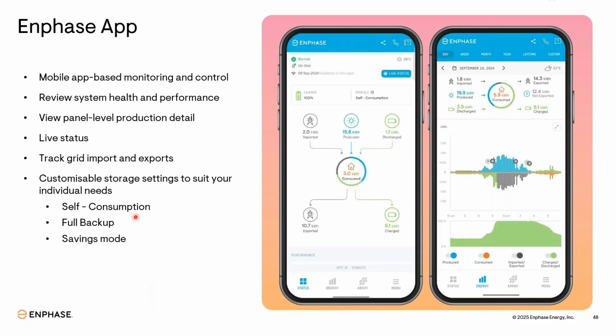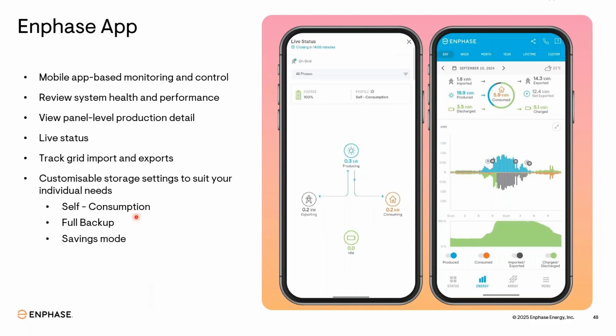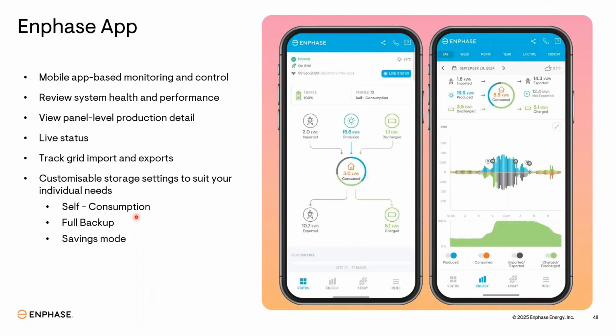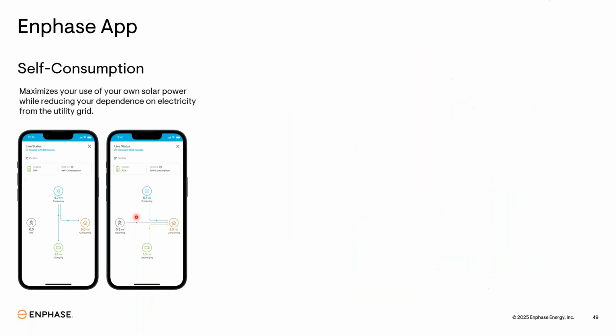So the app runs on three profiles. Self-consumption, full backup, and savings mode. You can operate your storage system in these three profiles. So what is self-consumption? Self-consumption is basically when you do not want to rely on your grid more. You do not want to import more, because this is used if a time of day tariff comes, where in the peak hours the tariff is higher and in non-peak hours the tariff is lower. So you do have battery systems.